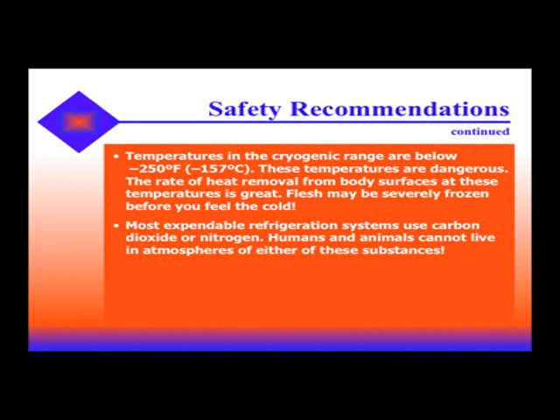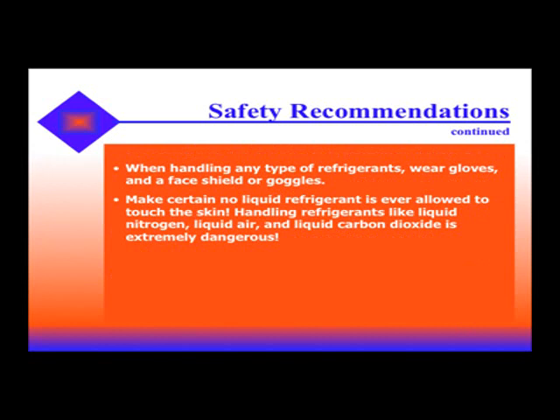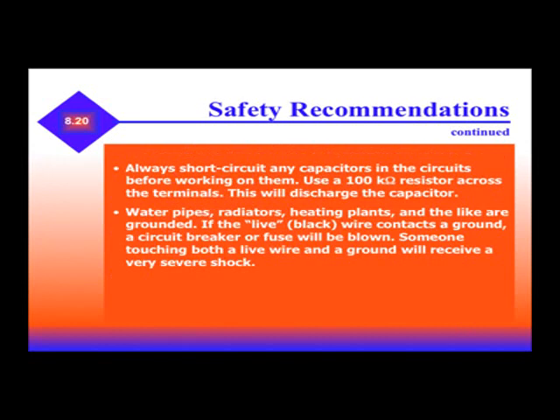Temperatures in the cryogenic range are below negative 250 degrees and can seriously remove body heat — skin and flesh may be severely frozen before you feel the cold. Most expendable refrigeration systems use carbon dioxide and nitrogen, and humans and animals cannot live in the atmospheres of either of these substances. When handling any type of refrigerant, wear safety goggles, face shields, and gloves. Make sure that no liquid refrigerant is ever allowed to touch your skin. Handling refrigerants like liquid nitrogen, liquid air, and liquid carbon dioxide is extremely dangerous. Always short-circuit any capacitors to discharge them. Always be sure that water pipes and radiators are grounded — if the live black wire contacts the ground, a circuit breaker or fuse will blow, and someone touching both a live wire and ground may receive a very severe shock.